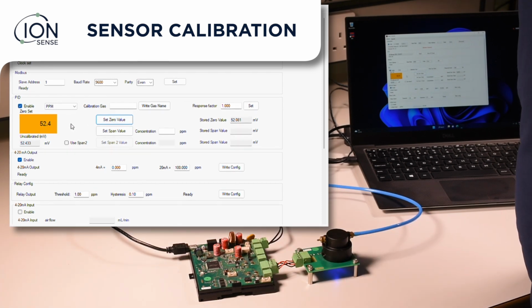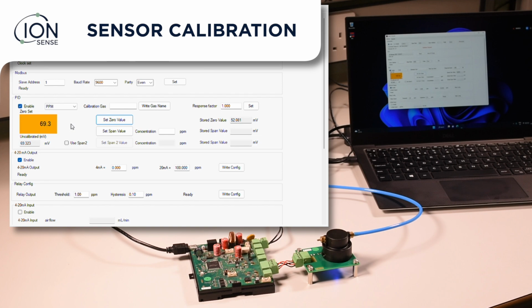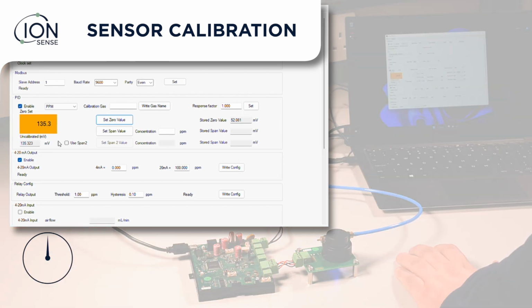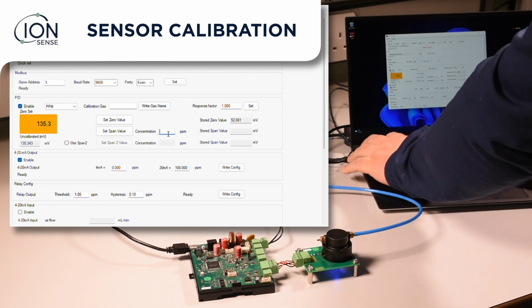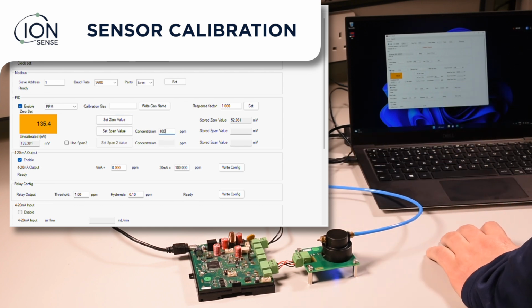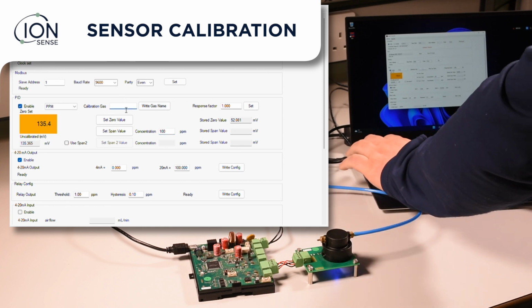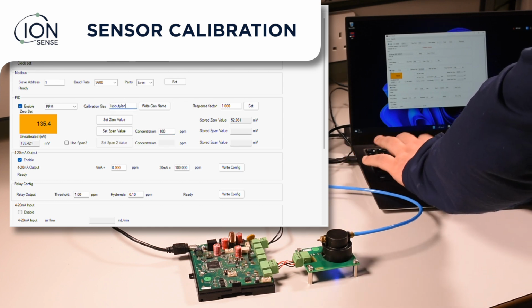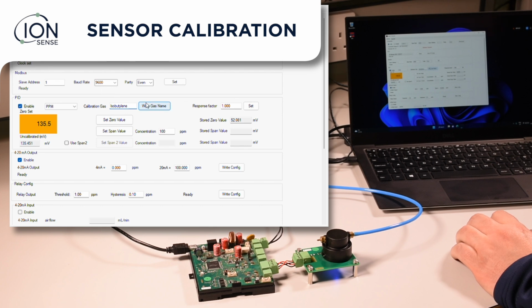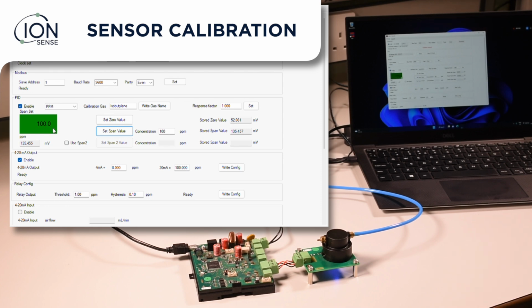Disconnect the zero gas and connect the SPAN gas. As the SPAN gas comes through, the reading will rise and stabilize. Once stable, enter the concentration of gas being used. The name of the gas. And click the Set SPAN Value button. If the calibration is successful, the window will turn green, and the previous millivolt reading will be replaced by a ppm concentration.